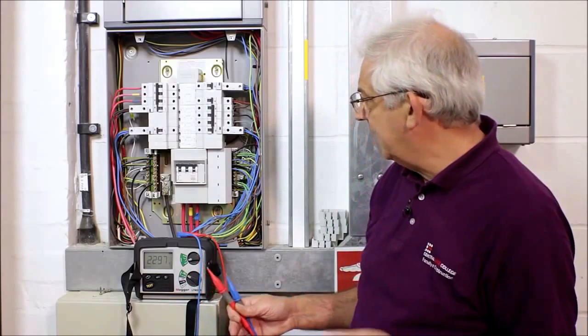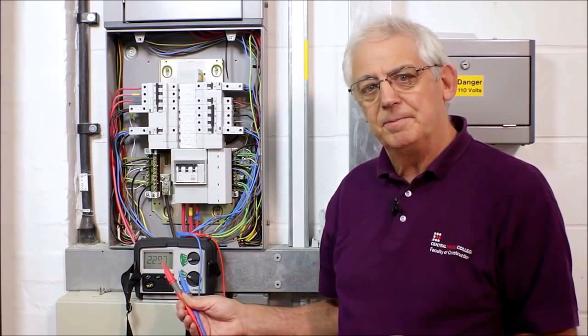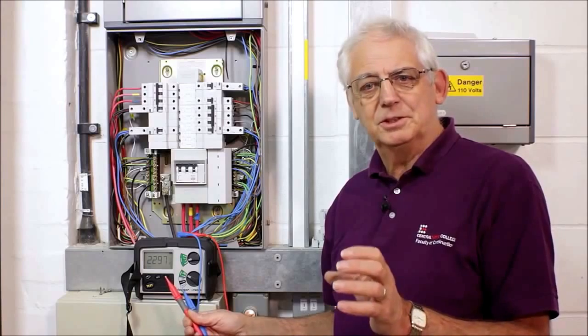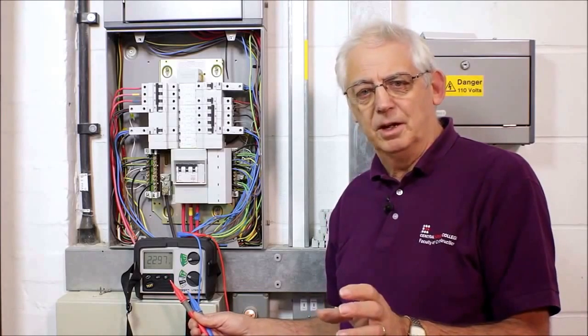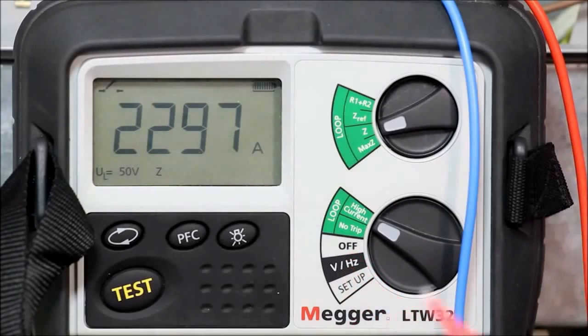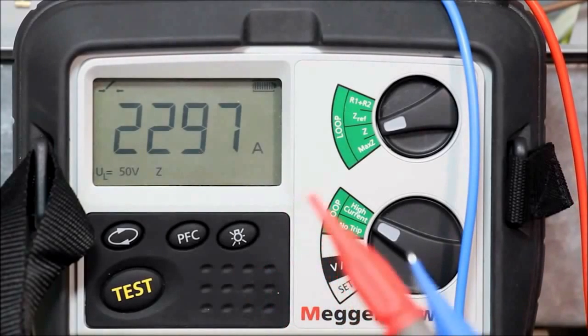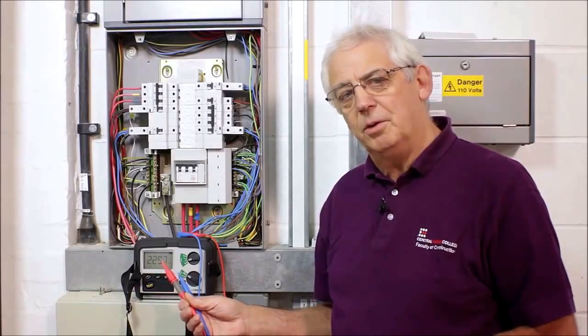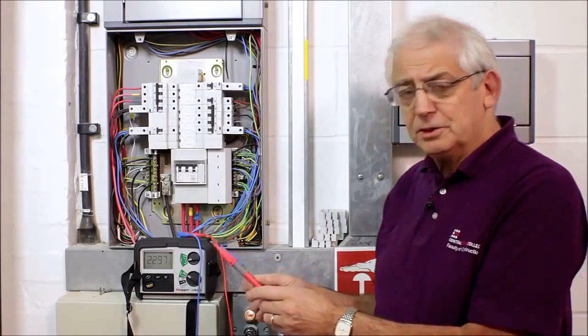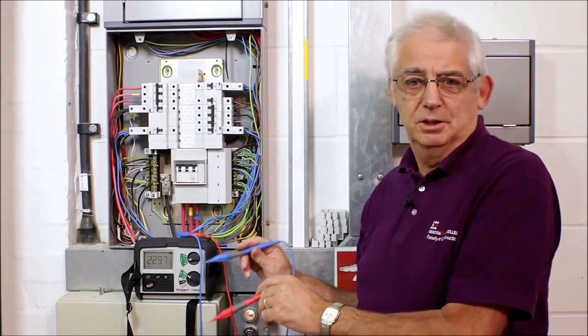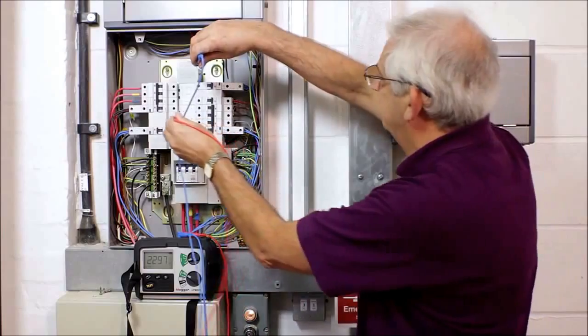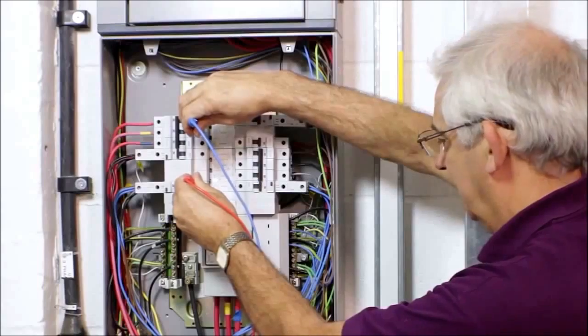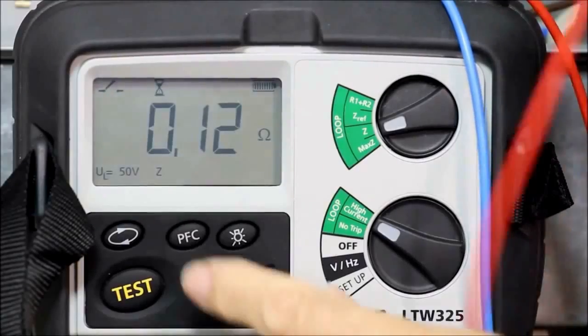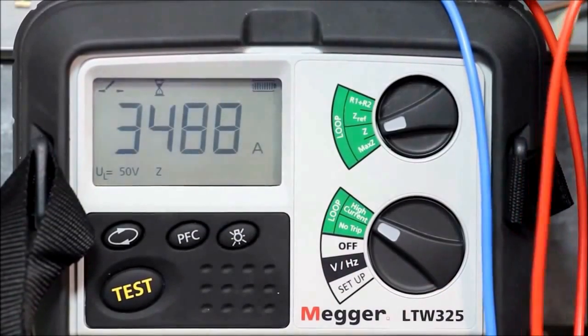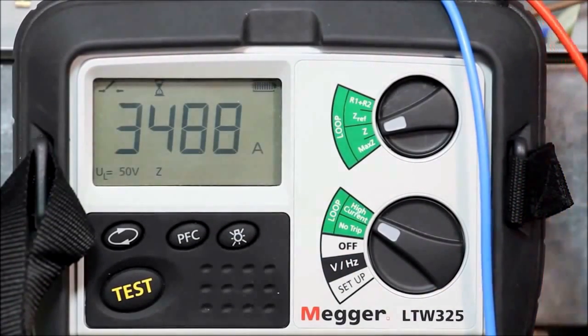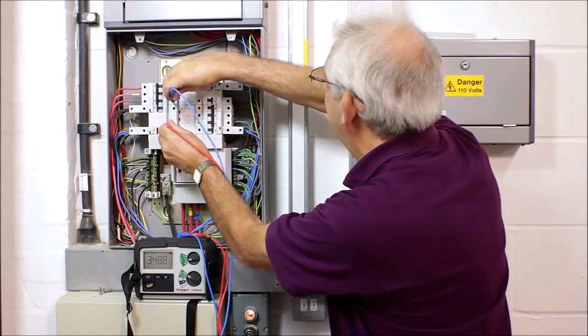Some instruments can test between 2 lines. You need to make sure that your instrument is capable of doing that, because the current that could flow is quite high. This instrument can manage that okay, so just out of interest, we'll do a reading and we'll see what value we get. First of all, I'll go between L1 and L2, or in this case, red and yellow. And I've got 3,488 between red and blue.